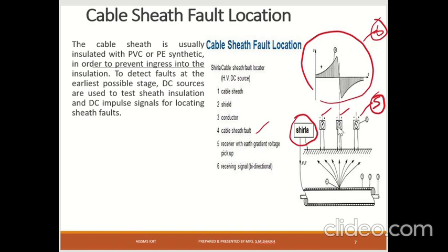Okay, and therefore this receiver is also pointing towards the right side, whereas the middle one is showing the null deflection, and the right side is pointing on the left side, indicating that the fault is somewhere in the middle or near the central receiver.